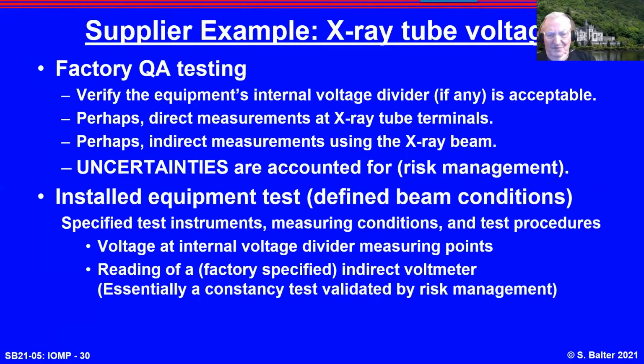Equipment is now shipped and installed. The manufacturer's team has specified equipment, measuring conditions, and procedures. They're going to use this internal voltage divider if it's provided. They may use a very specific indirect voltmeter. And again, this is the factory saying use model 1, 2, 3. Look for this as a constancy test. It's not an absolute test.